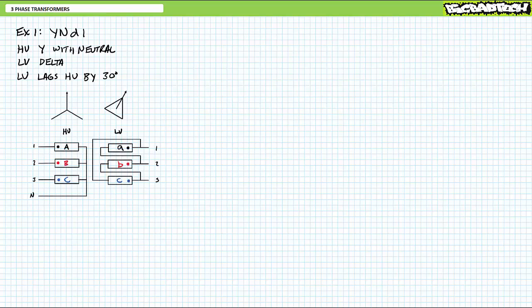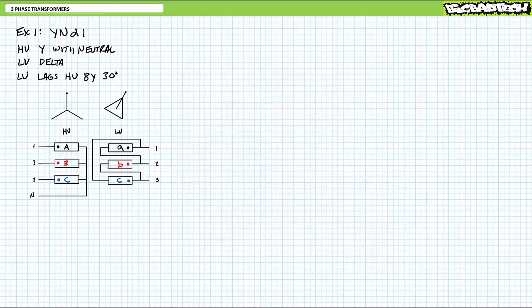Let's take a look at the simplified connection diagram for a YND1 configured three-phase transformer. Don't stress out too much about drawing simplified connection diagrams from scratch, since only the meanest instructor in the world would ever make you do this. But do stress out about the proper interpretation of an already constructed simplified connection diagram. Most of the time, you'll have a simplified connection diagram on the transformer nameplate available, and it's up to you to hook it up exactly as illustrated, with zero points being awarded for creativity.